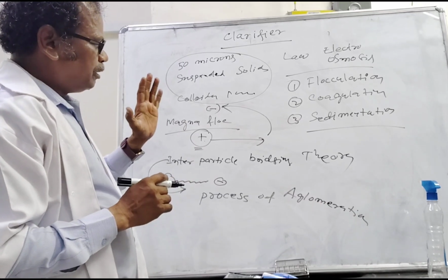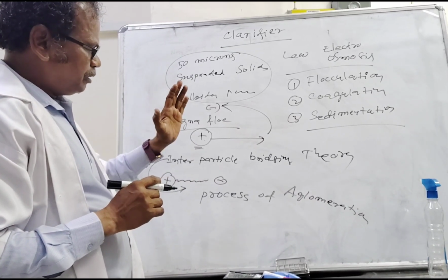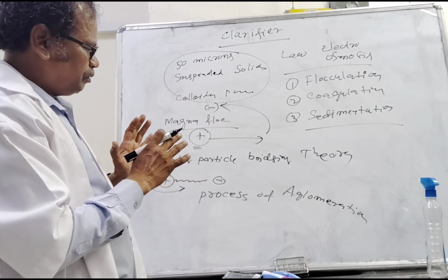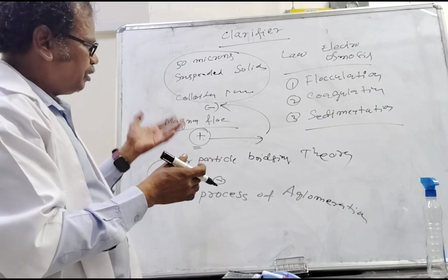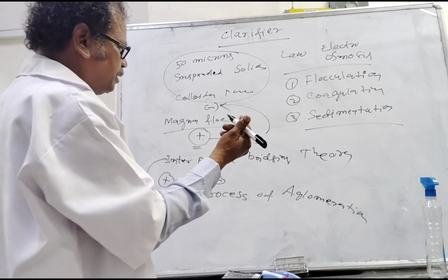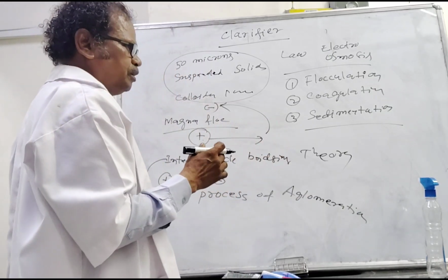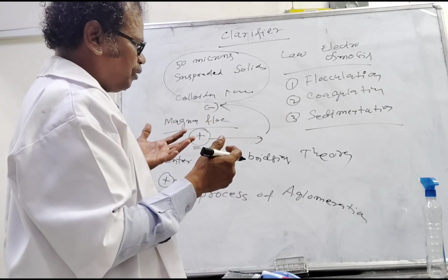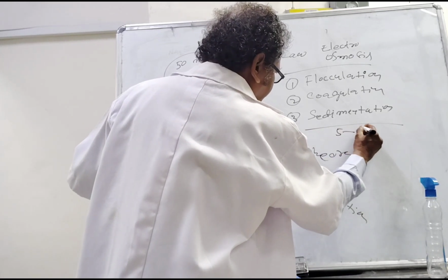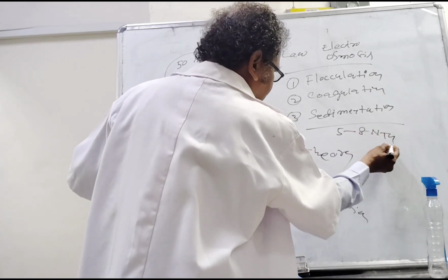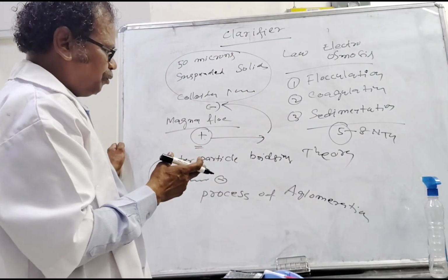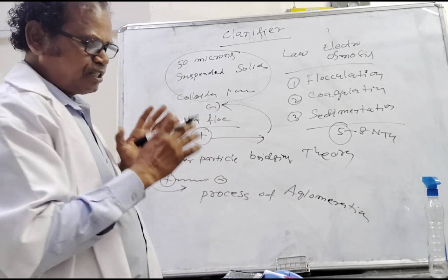All these mechanisms are running in our clarifier. The turbidity of the brine at the outlet of the clarifier is maximum 5 to 8 NTU in the worst case, but normally it is 5 NTU, and it then goes to our anthracite filter.